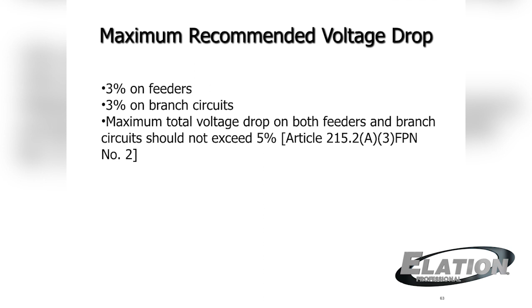So you can go to the supply, go to the panel, meter the power, meter the voltage there, and then while the gear is working, if you have a twofer to break it out, you can meter the voltage at the load end and do the math and figure out, is it more than 3% or less than 3%? If it's more than 3% drop, then you need to reduce the current or shorten the length of the run or use bigger wire if that's an option.